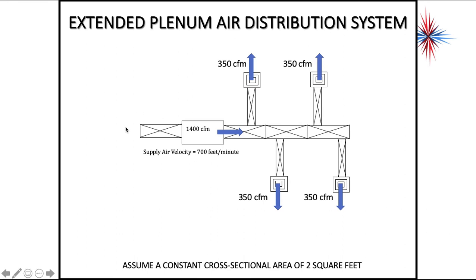This is an example of an extended plenum system. Let's assume a cross-sectional area of 2 square feet all the way through the duct work. Our supply velocity is 700 feet per minute. This gives us 1,400, because 2 square feet, 700 times 2 is 1,400.